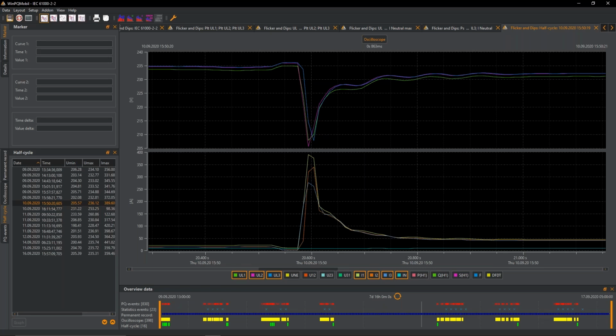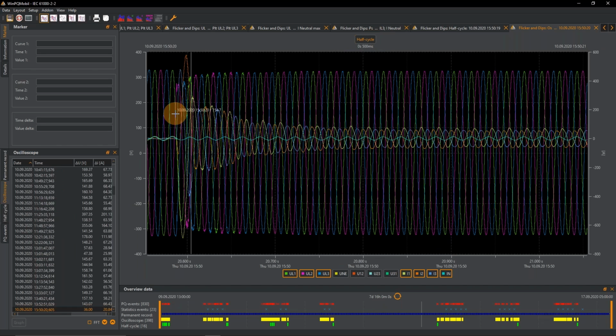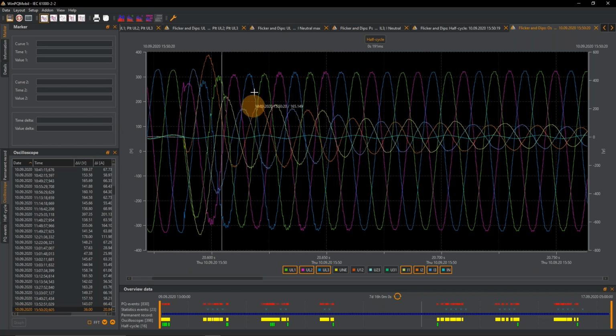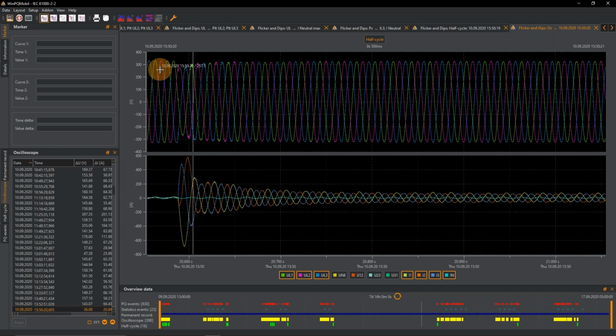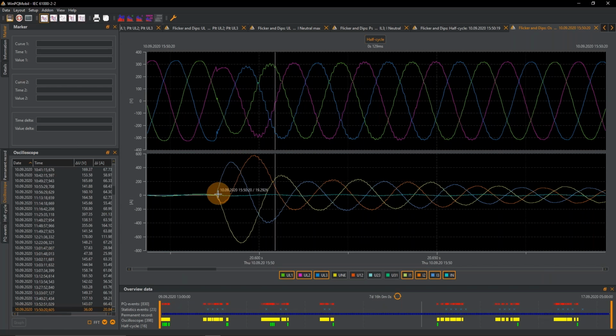So now I can see the fault record, and I can also jump to the connected oscilloscope fault record within here. So now I see the voltage and the current in one diagram, but yeah, there are too many lines. So I right click and click on divide axis. Now I get a better overview, the voltage and the currents. So this, for example, happened when a machinery was turned on, and we have currents that are tremendous. So the rush-in current, and this caused, obviously, a voltage sag. So this is one way to get to the fault record by the overview data.